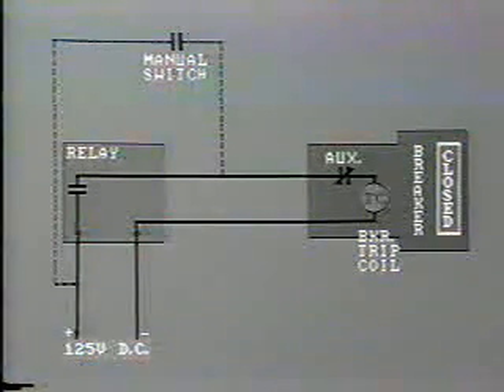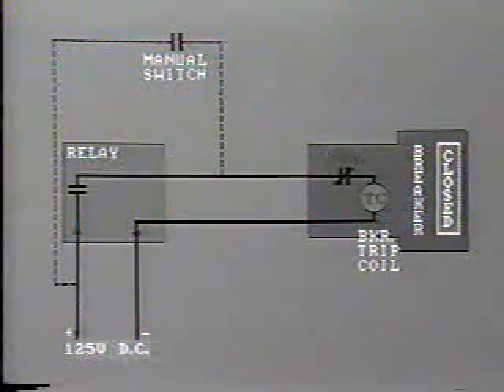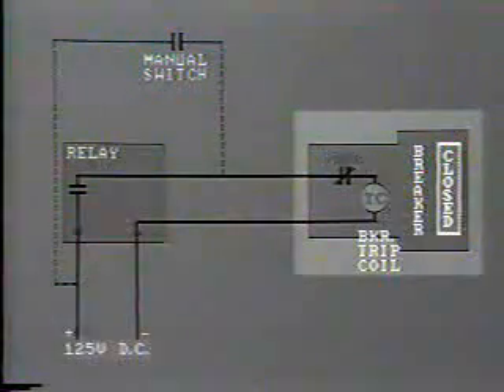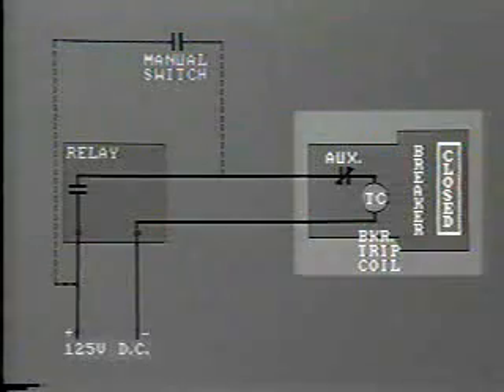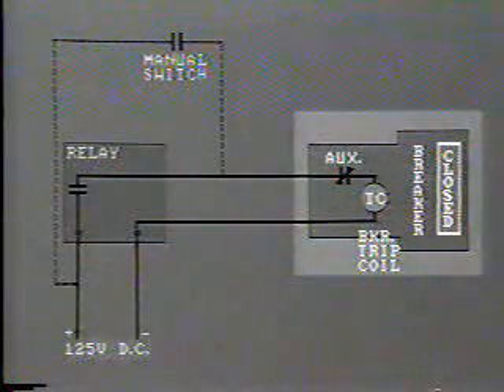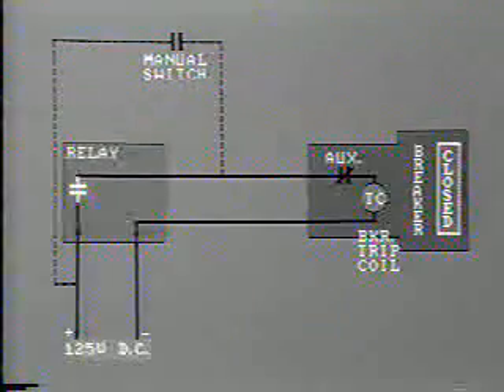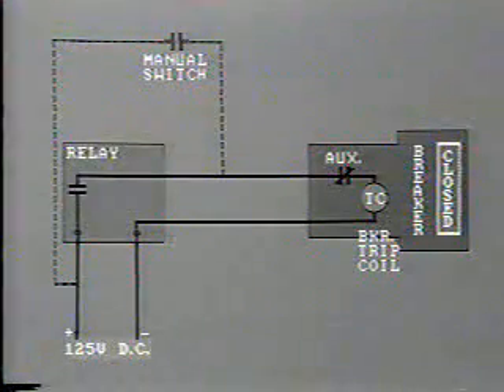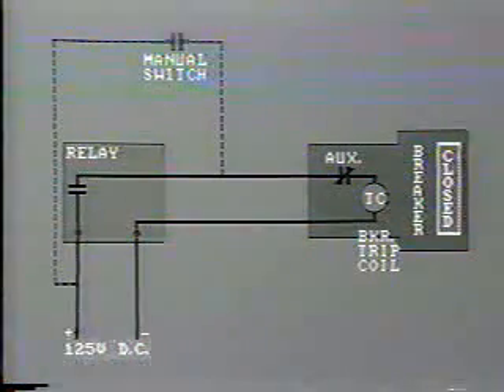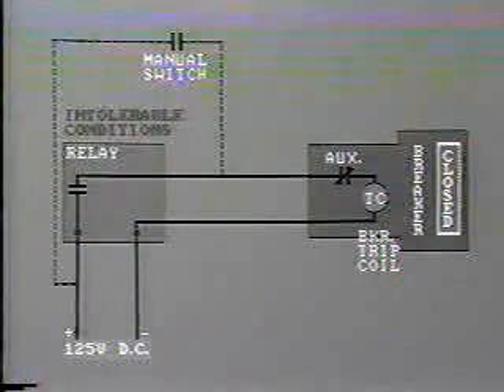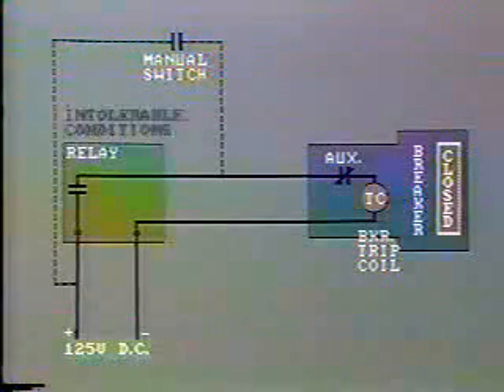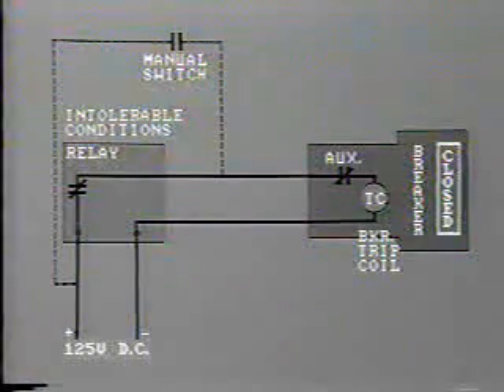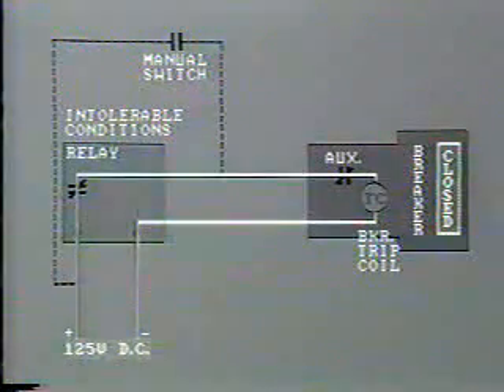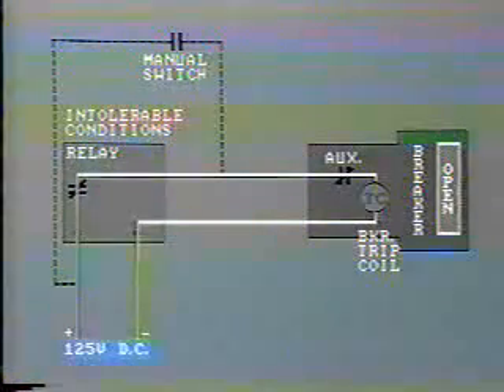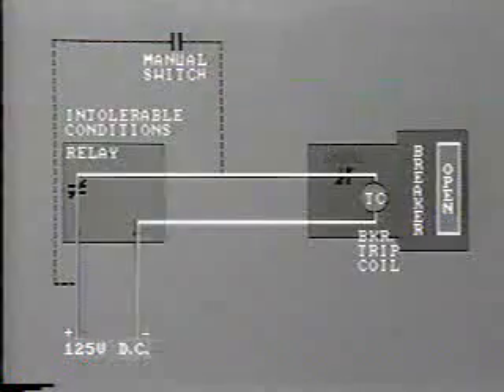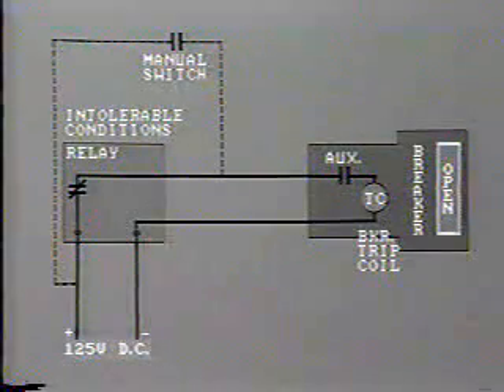Remember, the circuit breaker tripping coil and its auxiliary contacts are normally located at the circuit breaker inside the cabinet. This is probably in the switchyard, some distance away from the relay panel. However, relay operating contacts are located inside the relay. The manual switching contacts are normally located on the control panel. Now, when the relay operates due to sensing intolerable conditions, the relay contacts will close, and this now energizes the breaker tripping coil. This, in turn, causes the breaker to open and also causes the auxiliary contact to open, so breaking the DC tripping circuit.